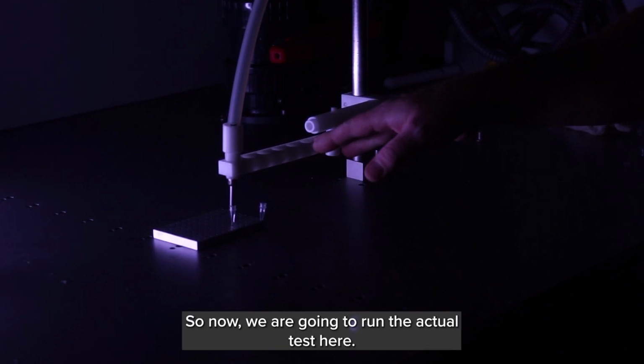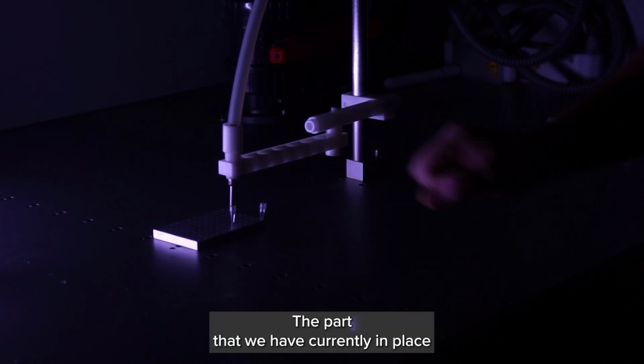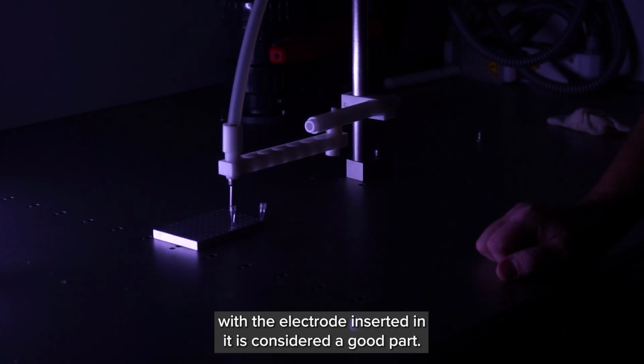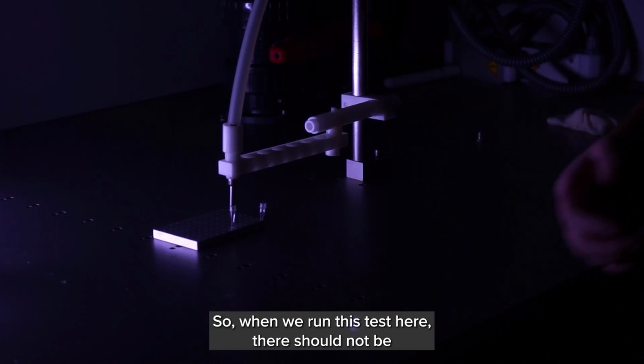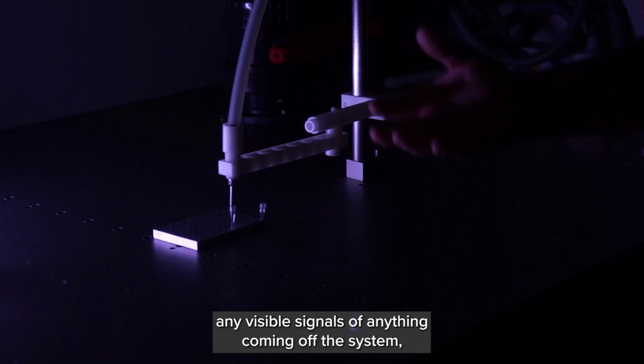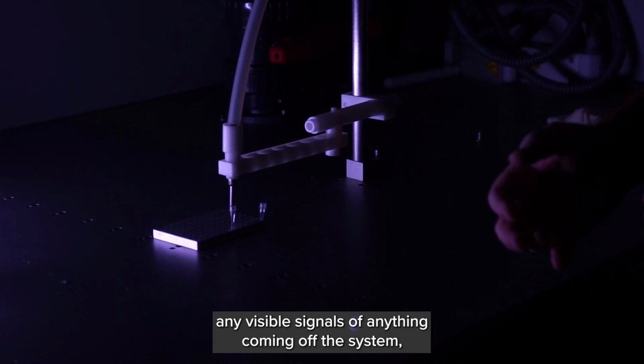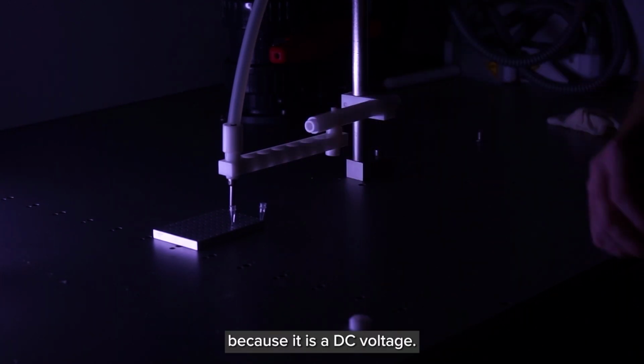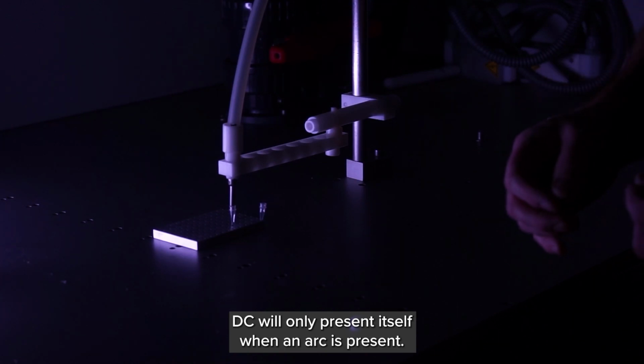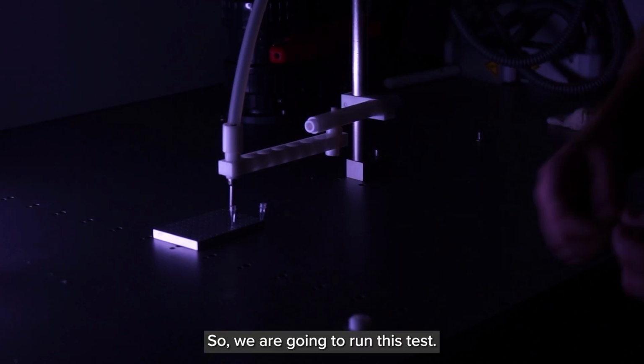So now we're going to run the actual test here. The part that we have currently in place with the electrode inserted in it is considered a good part. So when we run this test here, there shouldn't be any visible signals of anything coming off the system because it's a DC voltage. DC will only present itself when an arc is present. So we're going to go ahead and run this test.